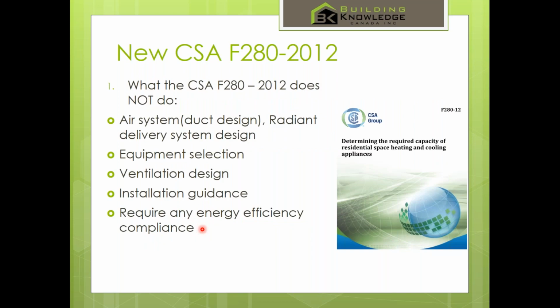The one thing to be very clear about, because there's been a lot of misperception about what the CSA F280 is. Number one, it does not do air system design, and it does not do radiant design. All it does is give you a load. It does not tell you what equipment you should select, and it does not design your ventilation system for you, and it does not have installation guidance, and it does not require any energy efficiency level of any kind. It simply tells you what the heat load is and what the cooling load is. That's it. To do these other things, you have to move to different standards or to different areas within the code.